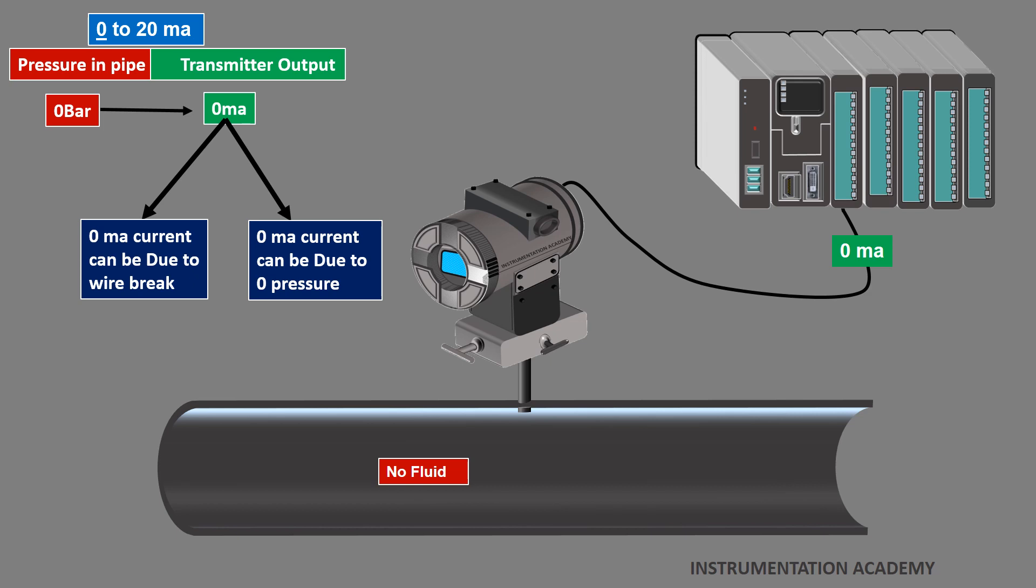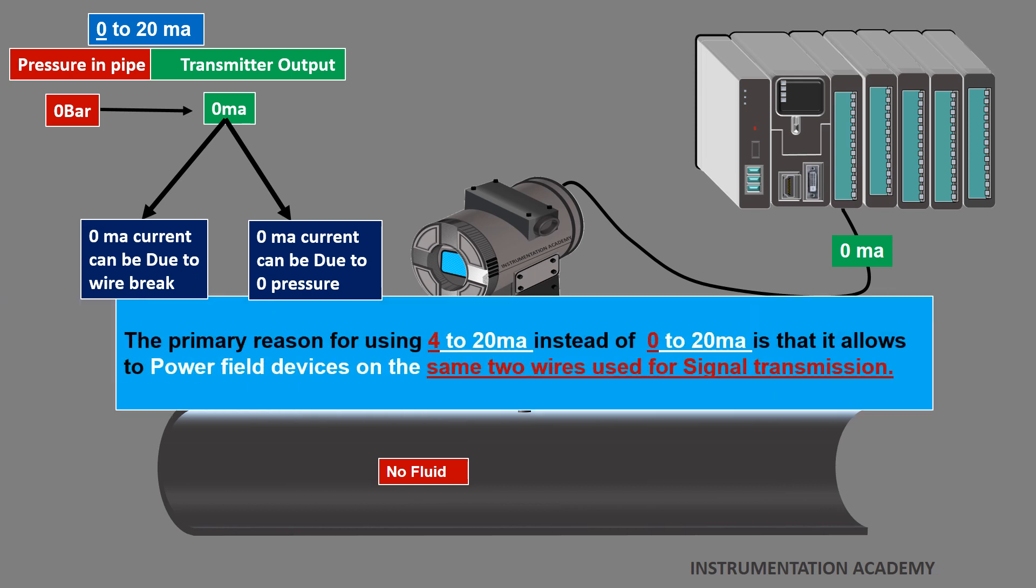The primary reason that 4 to 20 mA is used instead of 0 to 20 mA is because it allows to power the field devices on the same two wires that is used for transmitting signal.